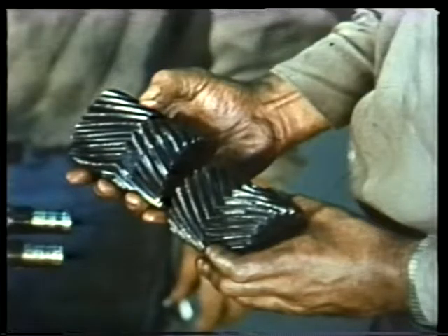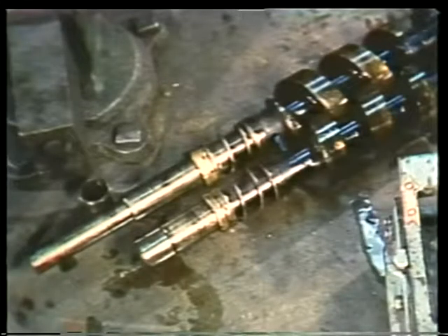That completes disassembly, cleaning, and inspection. We now know which parts must be replaced: the timing gears and two of the mechanical seals. Otherwise, our inspection showed that the parts of the pump are ready to be put back together. In a moment, we'll see the procedures for reassembling the pump and installing the new parts. But first, read through segment 3 of your text and review the material with your instructor.